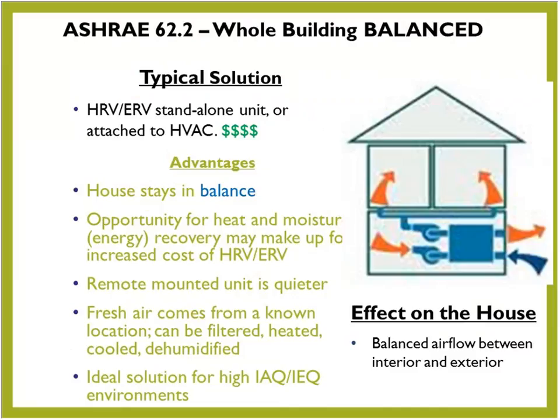All right. So let's move on to balanced. The balanced approach, again, the ideal situation here, we're doing some heat recovery. We're not creating positive or negative pressure, but there is a significant cost increase up front especially. And because you've got usually 2 motors in the HRV or ERV running, and oftentimes the install in our market is to interlock that with the furnace motor, not only do we have the operating cost for the HRV, ERV, we have the operating cost of the furnace motor distributing that air throughout the building.